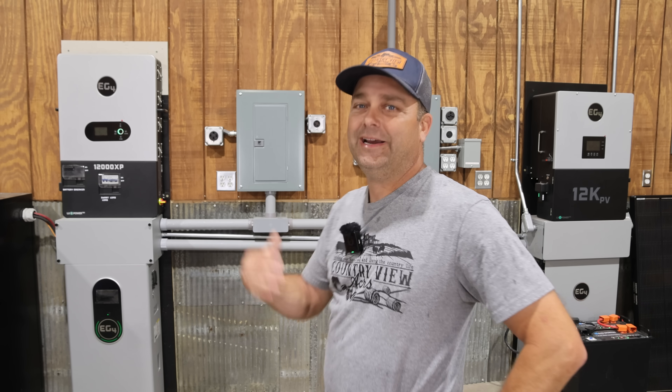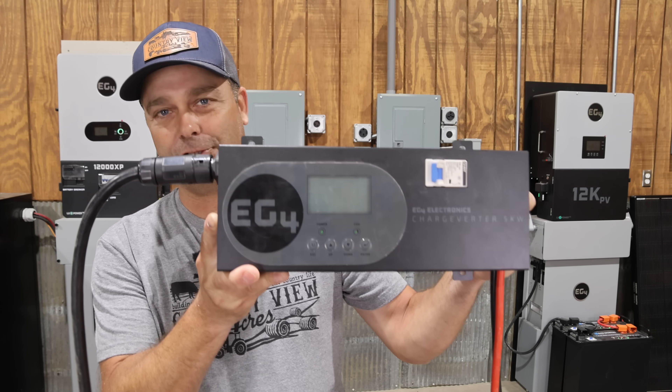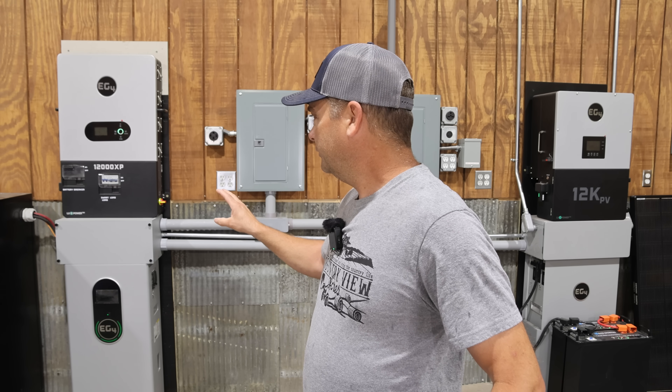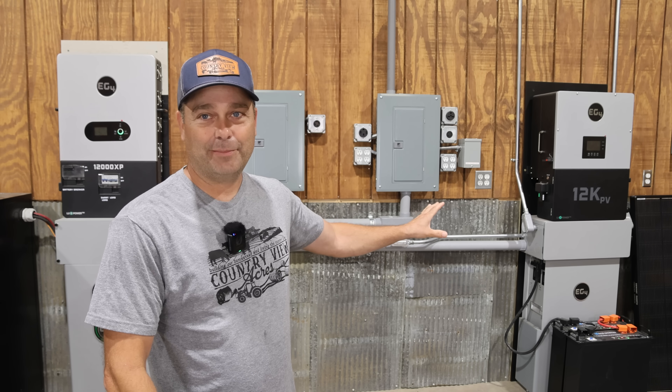Now that I've got the smart port wired up, what am I actually going to use it for? You can see behind me I've got a few different solar power systems — this one specifically is used to power this workshop. There are some weeks I'm out here three days working and other weeks I'm only out here one day, so the power usage fluctuates quite a bit and is very inconsistent. There ends up being several days a week where there's a lot of extra power that doesn't get utilized. So what I'm going to wire up is the EG4 ChargeVerter — basically a 48 volt smart battery charger. What I'm planning is: when this battery bank gets full and I've got extra solar power, I'm going to turn on this charge inverter and have it use the extra solar power to charge the battery bank on my other inverter.